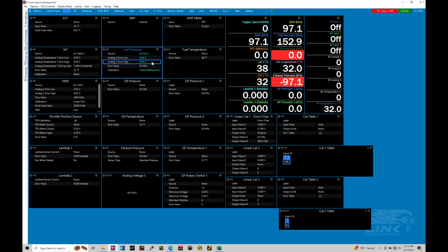If my fuel pressure sensor faults, I'll go in here and I'll allow it to read 0 kPa. So if there's a fault or a problem, that's what it's going to default to, and it'll flag that as a low or high error. So this should be okay for the fuel pressure. Again, I'm going to do Control S and perform a store to the Link. So this information now is stored permanently to the Link unless I go in and alter or change this.